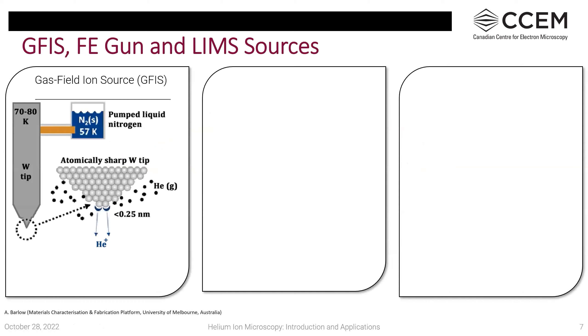Comparing the gas field ion source to a conventional field emission gun used by SEMs and the liquid metal ion source used by gallium FIBs: the GFIS tip is cryogenically cooled with pumped liquid nitrogen to 70–80 Kelvin. The virtual source size is less than 0.25 nanometers due to the atomic source, giving a probe size down to 0.3 nanometers. This source has very high brightness, low energy spread, and small wavelength, which minimizes diffraction effects.